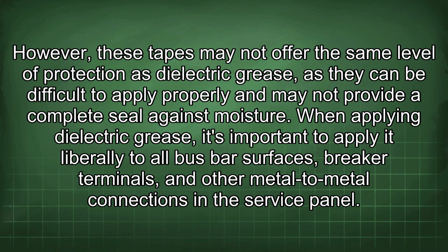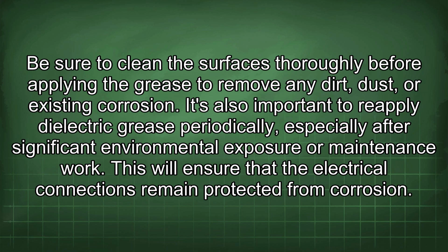When applying dielectric grease, it's important to apply it liberally to all bus bar surfaces, breaker terminals, and other metal-to-metal connections in the service panel. Be sure to clean the surfaces thoroughly before applying the grease to remove any dirt, dust, or existing corrosion.